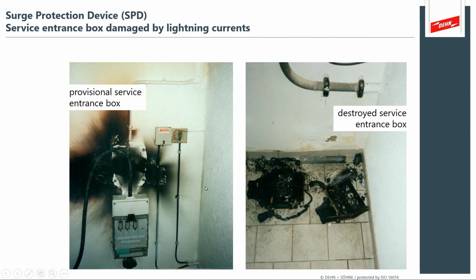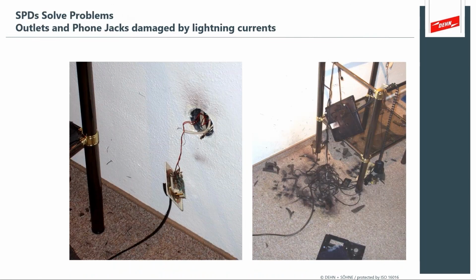What's important about the service entrance is to be sure to apply lightning protection SPDs that are rated for full lightning currents. And these are just examples showing the introduction of fire from the surge event. This was not an actual direct lightning strike. This is lightning that's coming in and the surge protection device is trying to control that. Here's a couple of nice photographs of what can happen well within the building. This is not at the service entrance. These are at the AC power outlets or at the phone jacks within a building. And here you can see the fire damage that you can get from what are actually small wires.